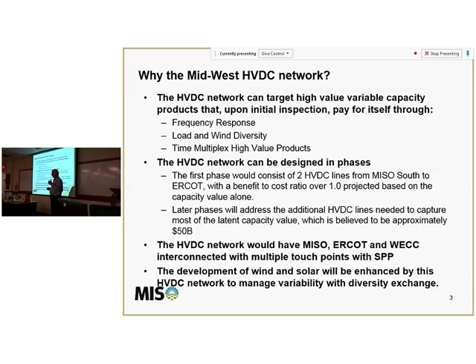But if you're going to build one transmission line, the underlying system will constrain the loading on that line to the contingency that could be taken by the underlying system. And therefore, it's generally less expensive to build at an existing voltage than to increase the voltage if you're going to build one line. If you're going to build two lines, you can get 50% of that line or more backed up by the other line, and then you have the underlying system. And that usually breaks out about even. You could do it one way or the other. And most people will do it with the existing voltage because they're more comfortable with it.